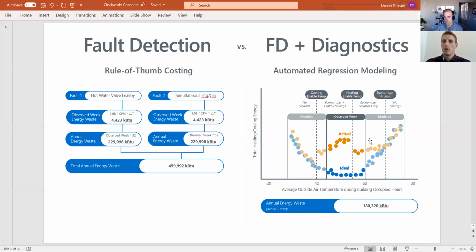So you need to observe a period of time that's representative of your conditions. Say we detected a leaking hot water valve during an outside air temperature range of 50 to 60 degrees—we then need to apply that regression analysis to model the projected savings for the rest of the year.